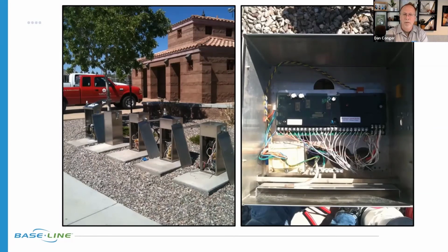You don't need a new concrete base. Each of those conventional zone wires was numbered, so we knew what zone it was in the previous control system. We wired it up and were able to do the search and assign, making sure it kept the same configuration for management and programming. In essence, we could have mixed those zones up any way we wanted in order to make it work. On this site, it was about 178 zones that we consolidated into one controller interface.